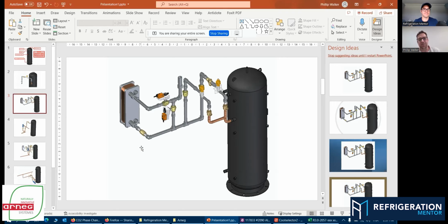And then let's go through this. This is now a typical subcooling system, and this is why I threw it in. So we got the high pressure expansion devices here. We're coming down here. We're going to go through a plate heat exchanger, or we do expanders. When we have air conditioning, basically the air conditioning suction side is coupled with the refrigeration liquid side, almost the same principle of an old school liquid suction heat exchanger. Except we use a special heat exchanger to expand the suction side. We get good subcooling out of that, and we drive the heat into the air conditioning side.